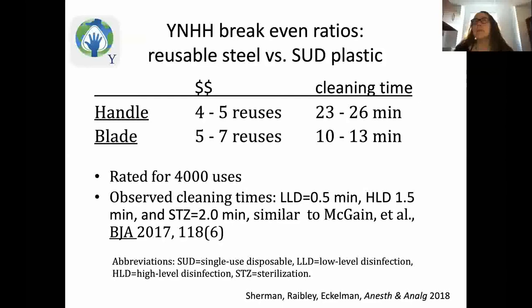Another criticism is, well, these things get lost and they're very expensive, so it's still more costly. I would say that what I just showed assumes, as the manufacturer guarantees, 4,000 uses of those stainless steel devices. In fact, when you refurbish the components, they're virtually indestructible. But we assume 4,000 uses, so that means 1/4,000th of the manufacturing and disposal, plus the cleaning and packaging, is compared to one disposable.